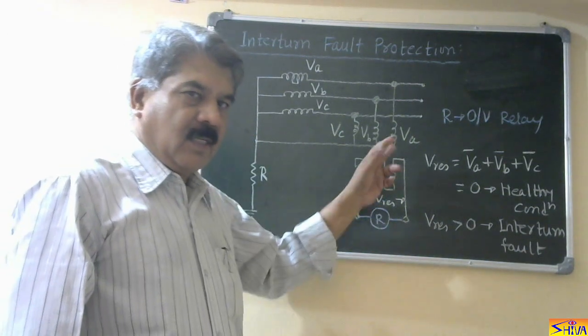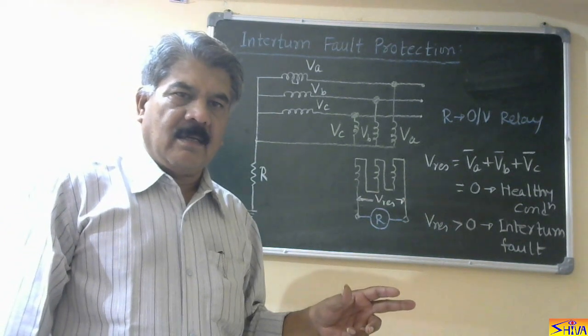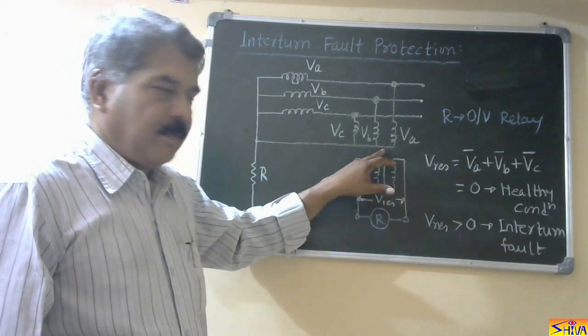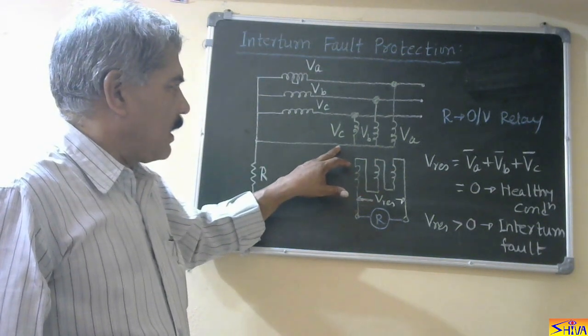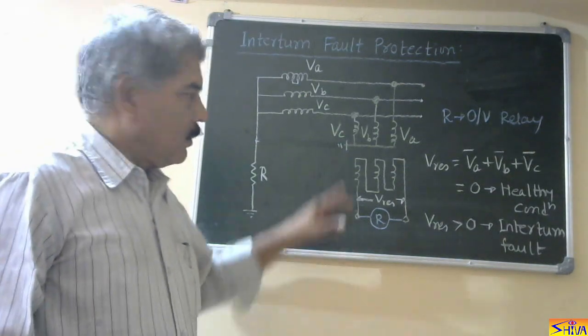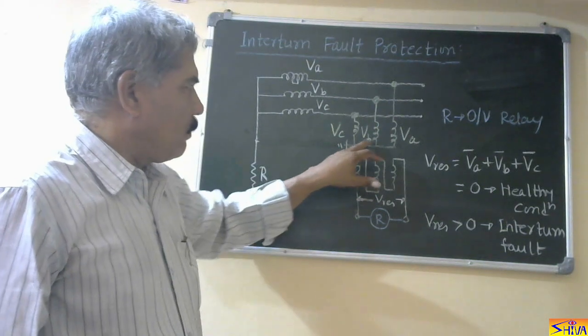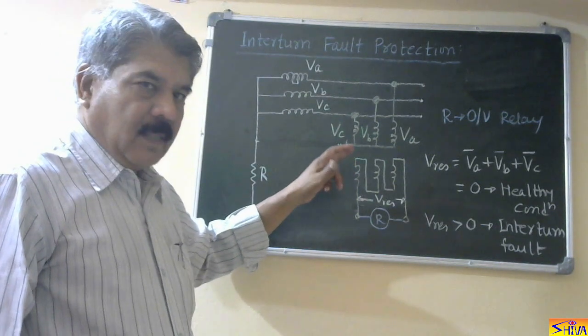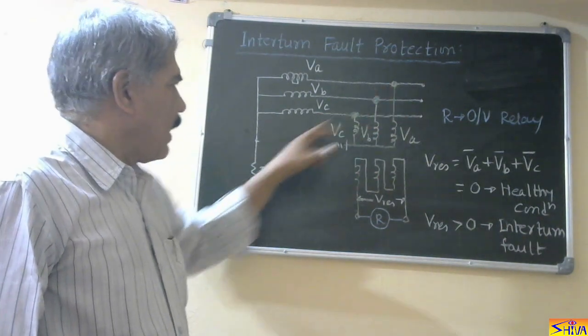This scheme using a star open delta transformer is useful for both single-layer and double-layer winding. Here you must remember the difference in the connection: the star point of the primary side is connected to the star point of the alternator. If instead we simply ground this point, the voltage Va measured will be between phase A and ground, Vb will be between phase B and ground, and Vc will be between phase C and ground — which is different from measuring between the phase and the neutral point.